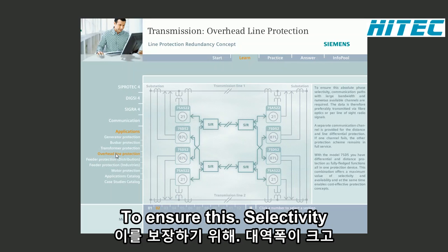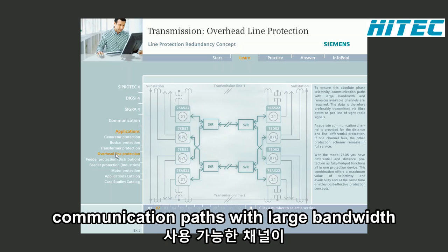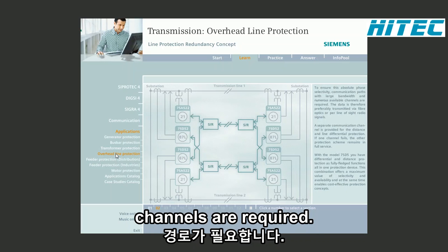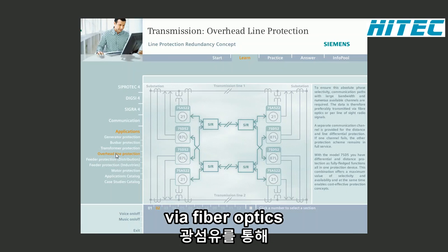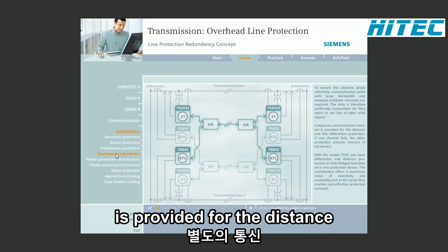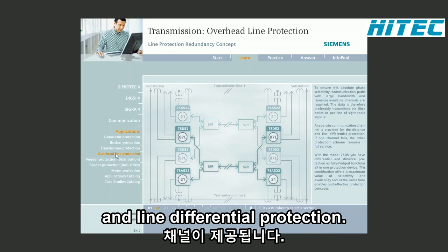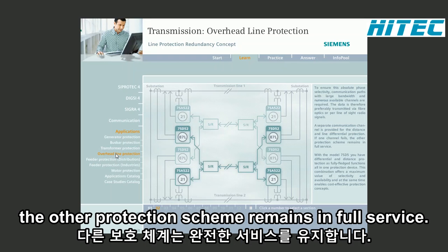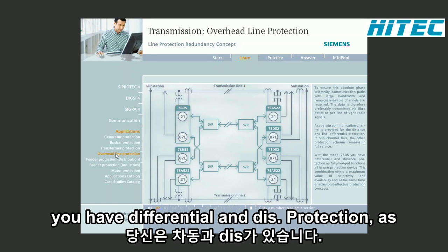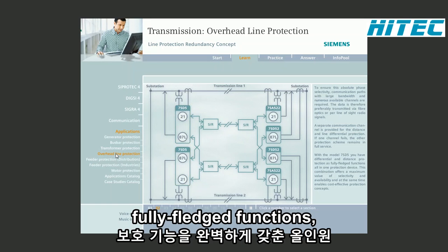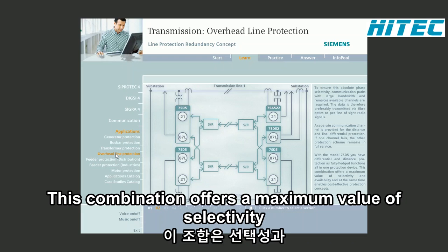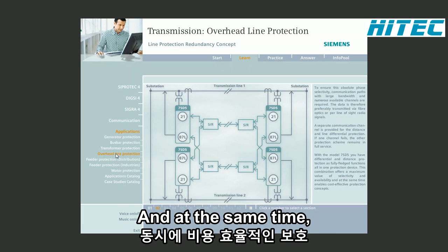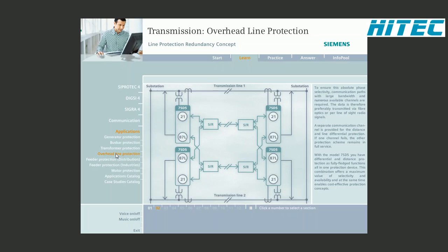To ensure this absolute phase selectivity, communication paths with large bandwidth and numerous available channels are required. The data is therefore preferably transmitted via fiber optics or per line-of-sight radio signals. A separate communication channel is provided for the distance and line differential protection. If one channel fails, the other protection scheme remains in full service. With the Model 7SD5, you have differential and distance protection as fully fledged functions, all in one protection device. This combination offers a maximum value of selectivity and availability, and at the same time, enables cost-effective protection concepts.